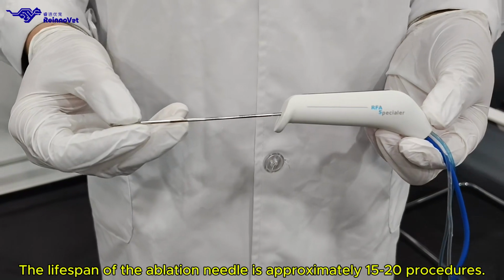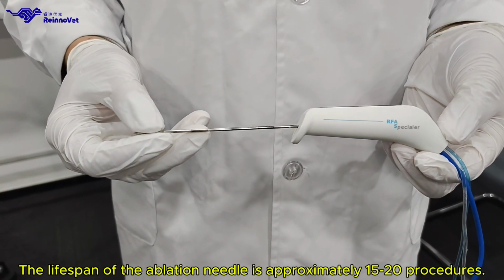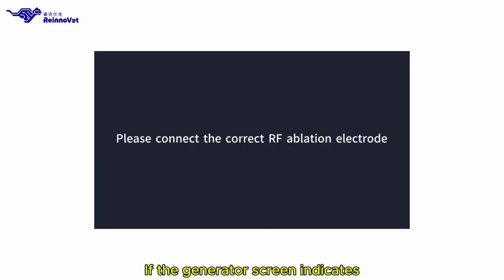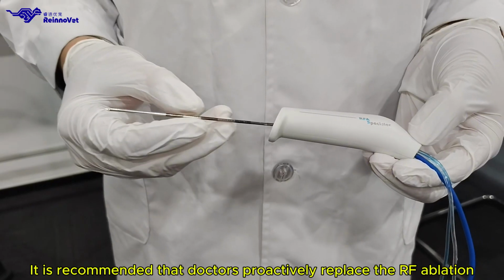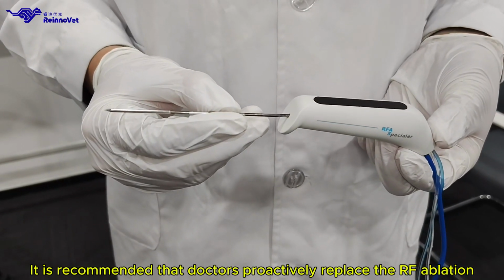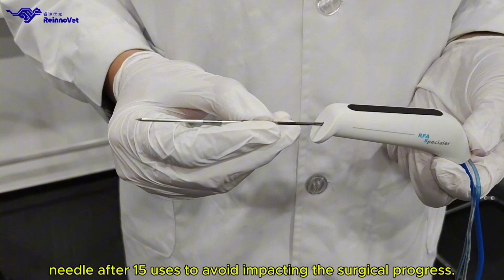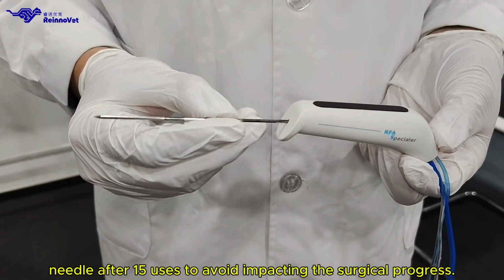The lifespan of the ablation needle is approximately 15 to 20 procedures. If the generator screen indicates that the needle has reached its lifespan limit, replace it with a new one. It is recommended that doctors proactively replace the RF ablation needle after 15 uses to avoid impacting the surgical progress.